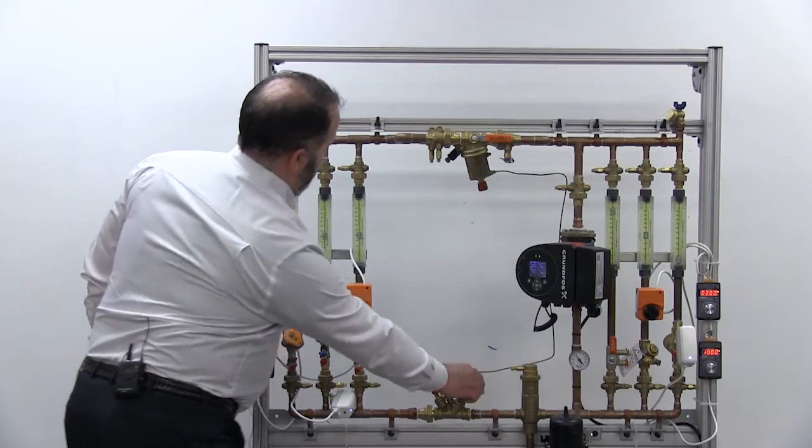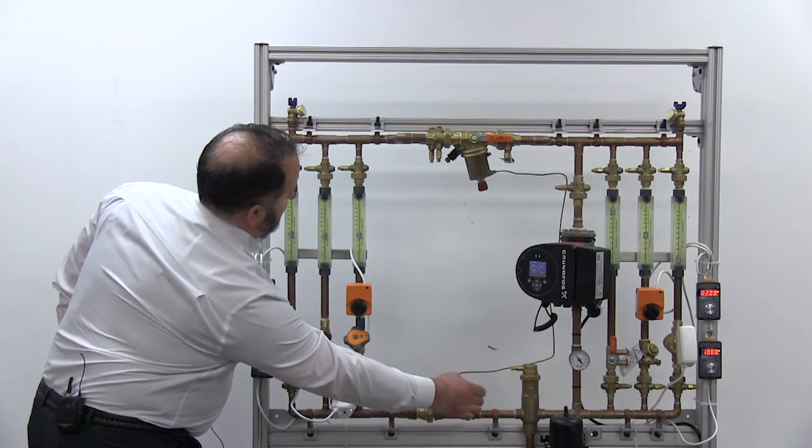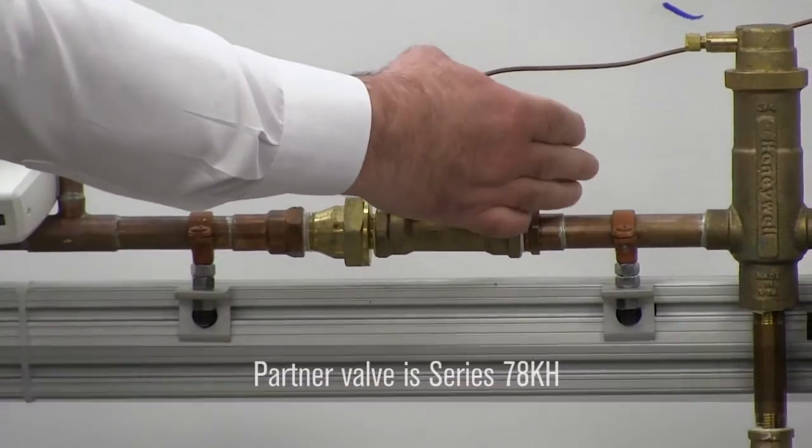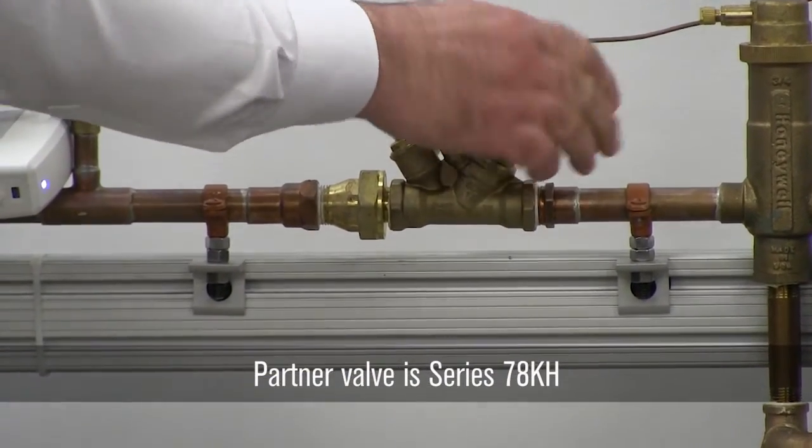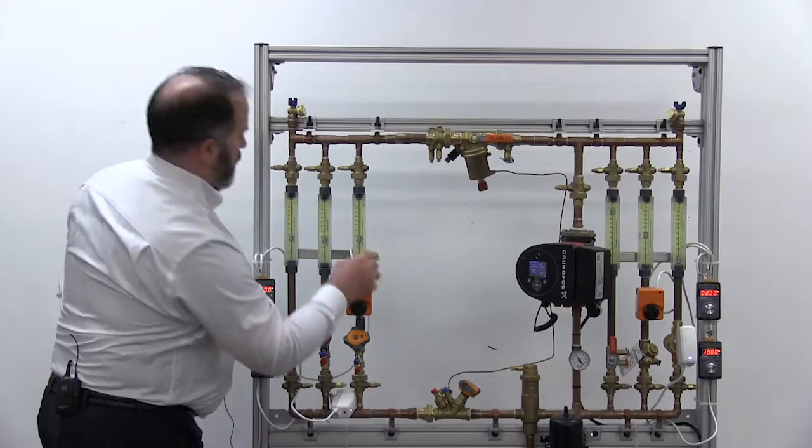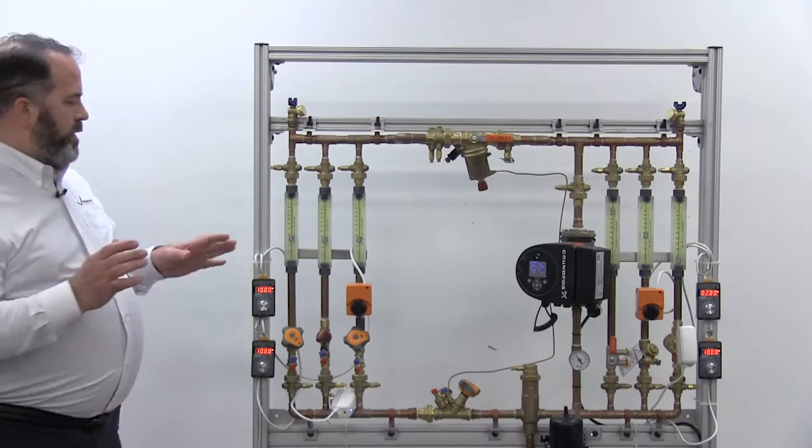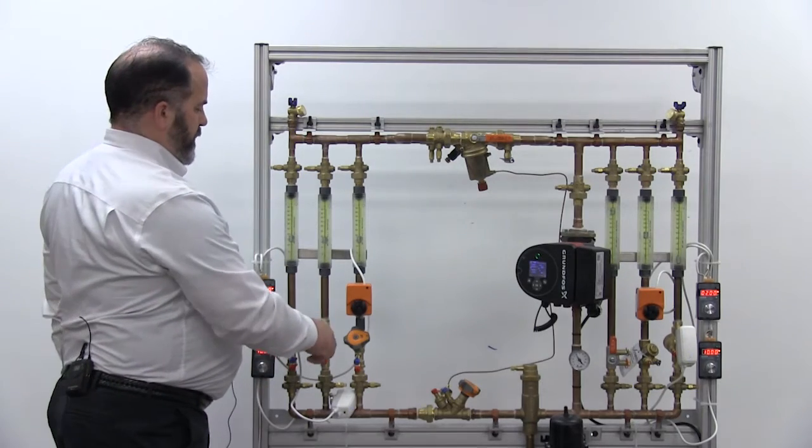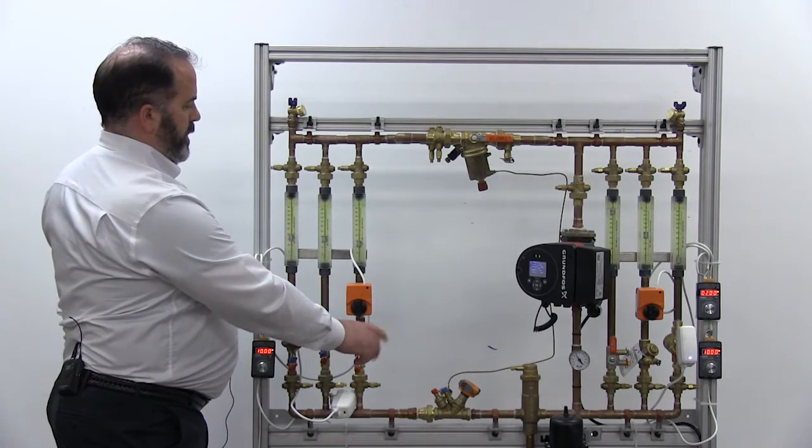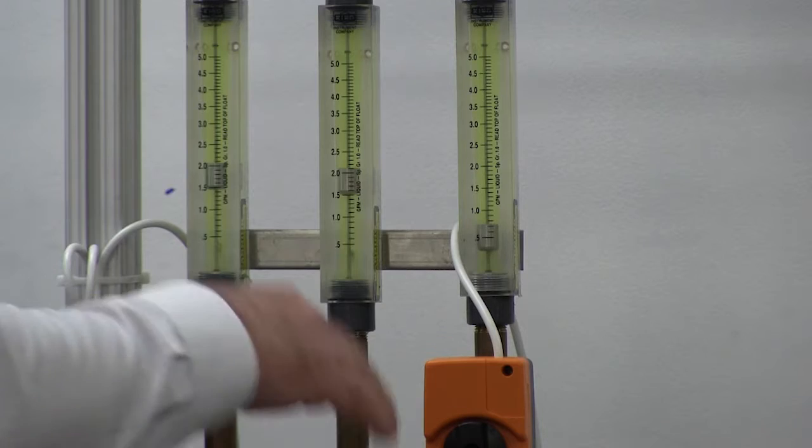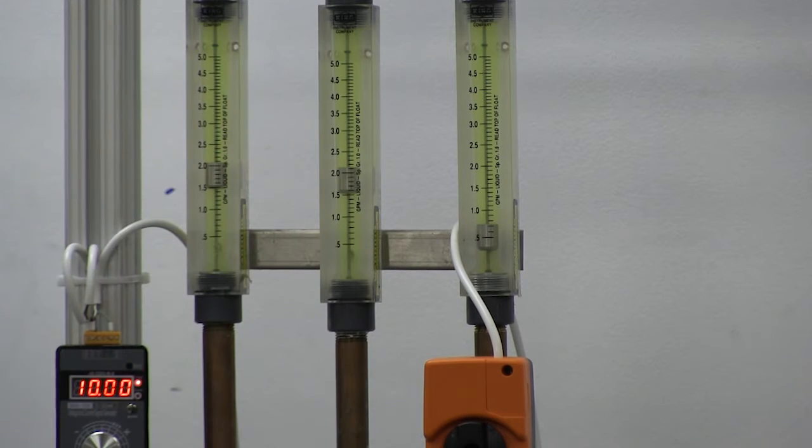So at that point we can use a partner valve to balance the system further and get ourselves down to what we'll call our 2 GPM design flow for each of these coils. You'll notice that as we make changes within this part of the system, as I close this valve down, these valves start to open further or the flow starts to go up into the other two coils and I'm winding up overflowing those two coils.